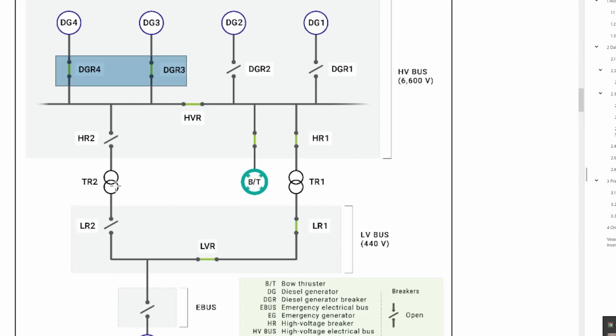It couldn't have come from here since these are open circuit, so it was coming from elsewhere along the line. It could have been a bad transformer, bad breakers causing something, a short somewhere in the low voltage bus, or something on the high voltage bus shorting. Good luck trying to figure out exactly what appliance was drawing too much current, if that's indeed what caused both breakers to pop.